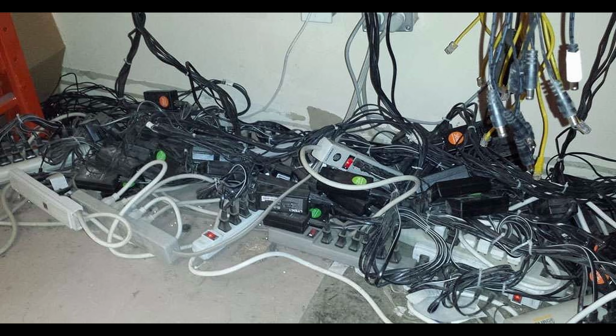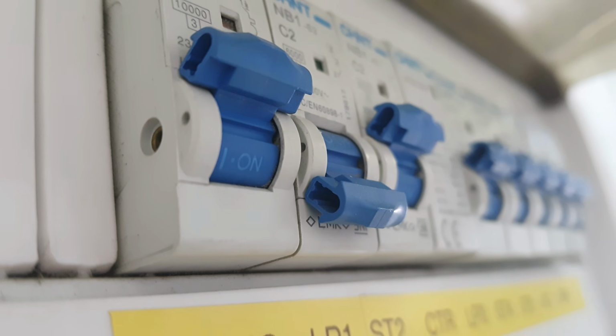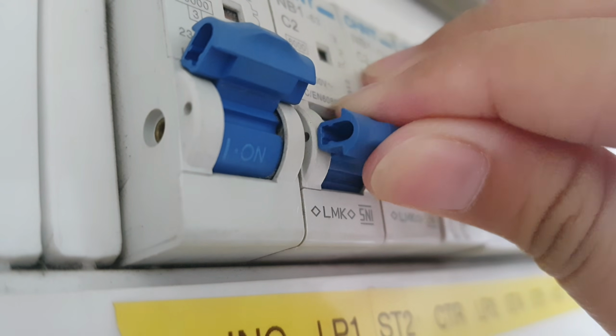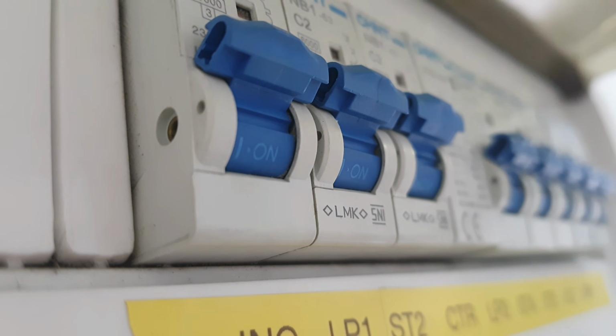Part of the job of protecting people is protecting the cables, and this is done with our protective devices such as our circuit breaker. When a fault occurs either by current passing to earth or overloading, a higher than designed current, in these scenarios it will cause the breaker to trip because it would have the appropriate cable and the breaker which would follow the regs, right? When we think of overloading, we might think of a chain of extensions which rely on a fuse to break the connection. But overloading could mean an entire circuit, say a ring main. We could easily plug too many high-powered devices, which would cause the cable to pull too many amps for its design current. Interestingly, it's not just sockets that could cause this overloading. Even a stalled motor can draw more current. A stalled motor draws way more current than its general operating current, which could cause this tripping effect.